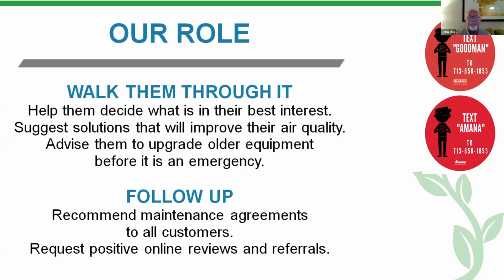And advise them about the mechanical part of it. Is the equipment old? Are we looking at replacing it before there's an emergency? A big one is, can the existing system support good filtration? A lot of times what I'm finding is that the ductwork is undersized, equipment is oversized and under-delivering, and to slap a good filter in place, things are going to go the wrong direction.